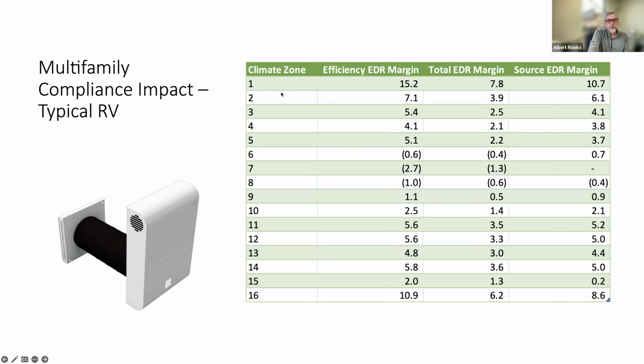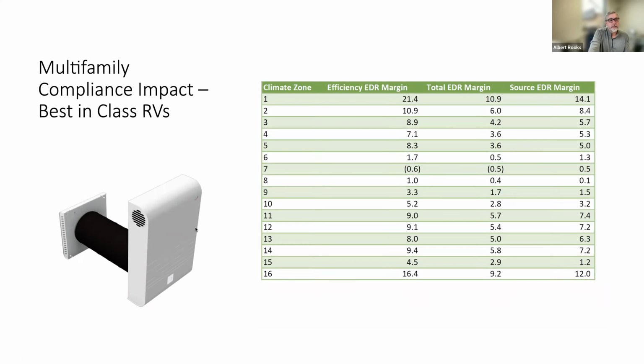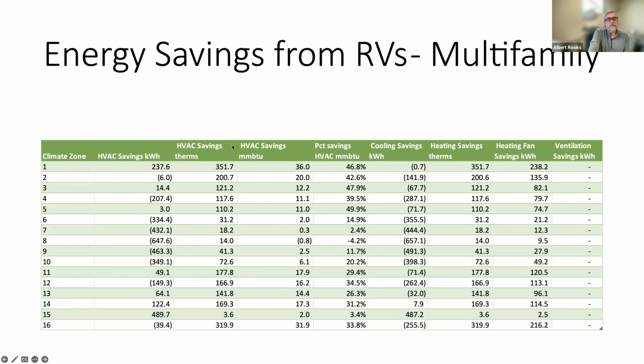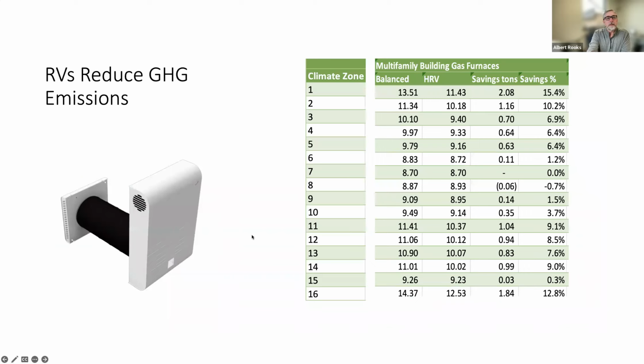So just basic equipment has a pretty strong effect, and basic equipment is in that 70% effectiveness range. In the 90% effectiveness range, the effects get even stronger, right? The 10 goes to 14, the 6 goes to 8.4. The numbers down here also look really pretty good. And then if we look at savings across different heating devices, we could be heating the building with gas, and we'd be looking at therms, or we could be using an electric source. All of these would have an impact, and using better heat recovery would cause less loss or gain in the building, and overall it all boils down to maybe looking at GHG savings, right?